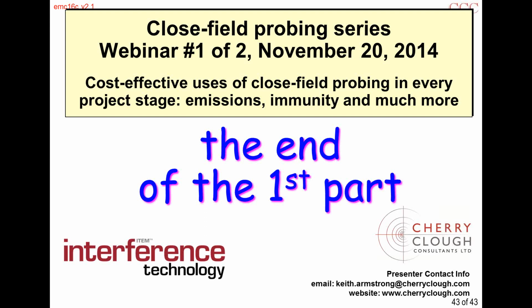You have to be careful on your Declaration of Conformity to say, I have applied the following test standards. And you list things like EN 55022 or whatever. But nobody knows what the word applied means, not strictly speaking. Now, applied could mean that you've used some other technical method. For instance, if you've got something like a digital watch that's running off a tiny little coin cell for so many years and it's only consuming microamps, there's no way in the world that even if it emits all that power the microamps is drawing at one particular frequency, it still won't be above the emissions limit. So you can use a technical argument in that sort of situation.